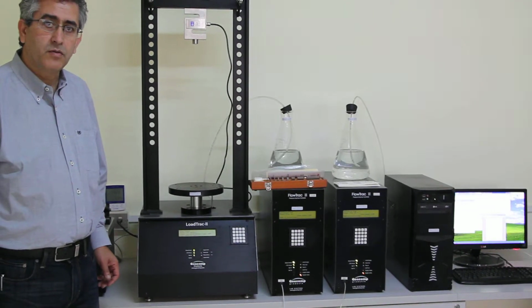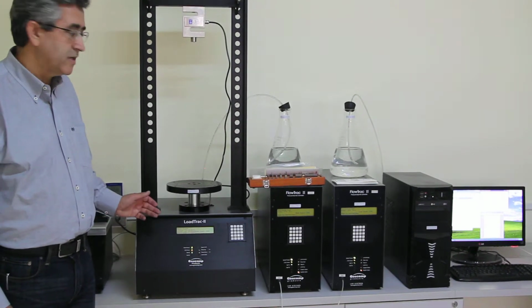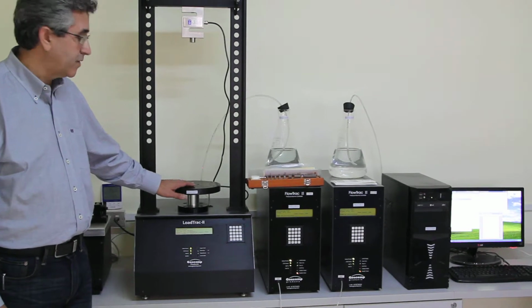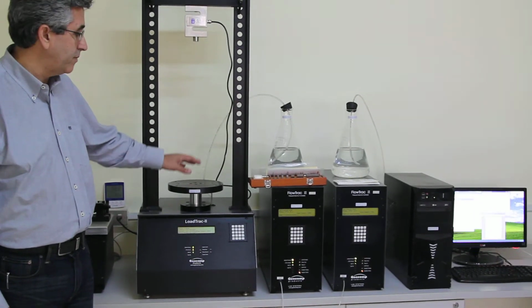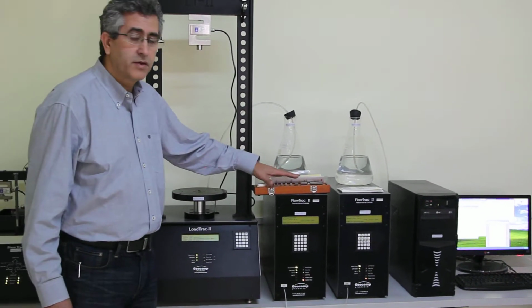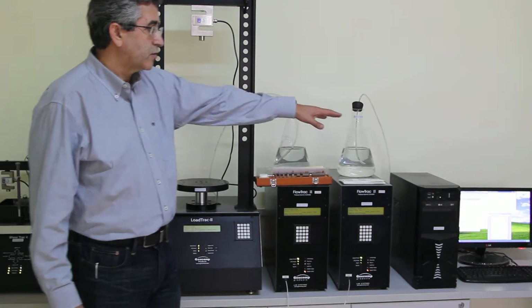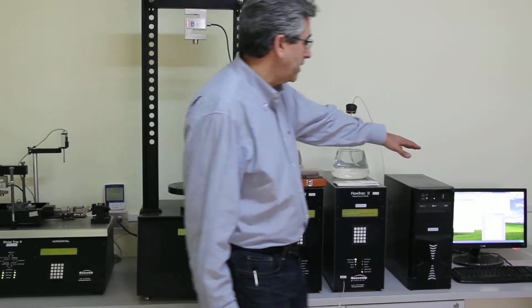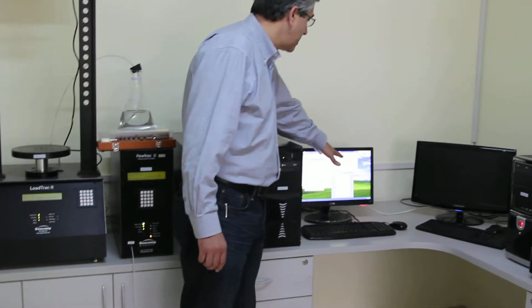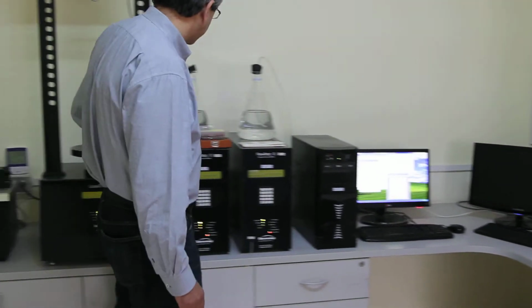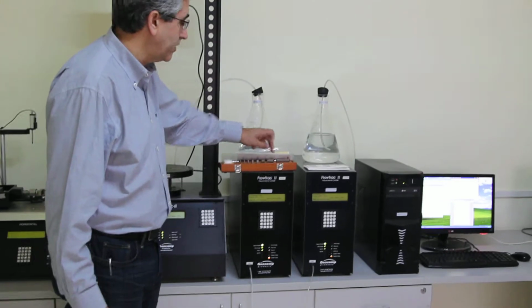Now we are ready to do our calibration for our displacement sensor. The platen has been moved out to about halfway to the middle range. We have our gauge blocks, they are ready. The software is open and the menu is open.